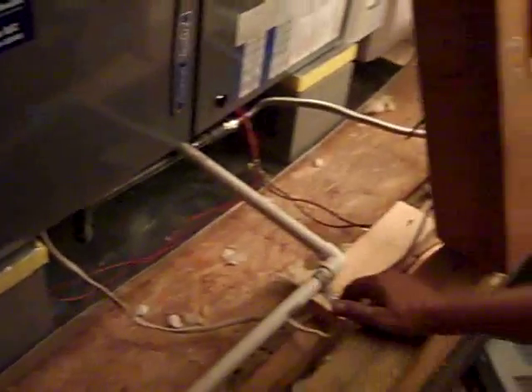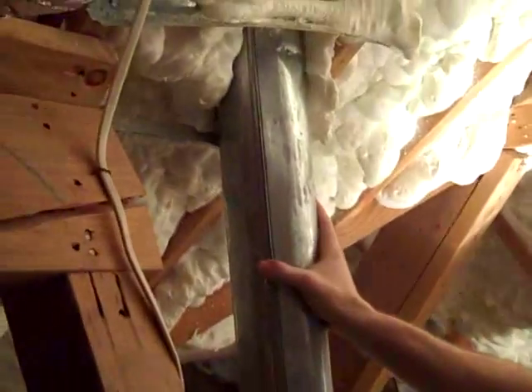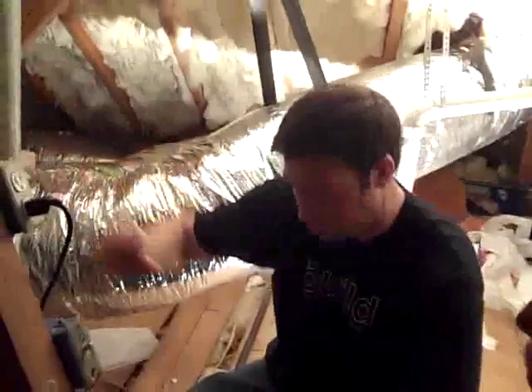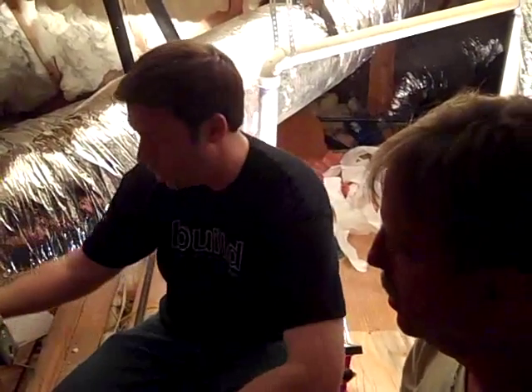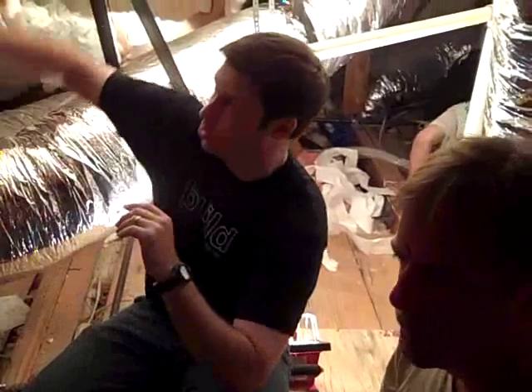We're still working on this house. There's a remnant from the old furnace here — this is the old flue that used to run right through the ceiling here. We're going to change this out to our concentric PVC flue. In the old furnace that was in here, which was 70-some percent efficient, it just had one heat exchanger. When that natural gas was burning, there was a lot of hot gases running through this flue and heading right out of the roof. Now that we're using a 95% efficient furnace, this furnace has two heat exchangers, and we're cooling down those gases by capturing more of that heat that normally was just going to run right through your roof and get dumped.